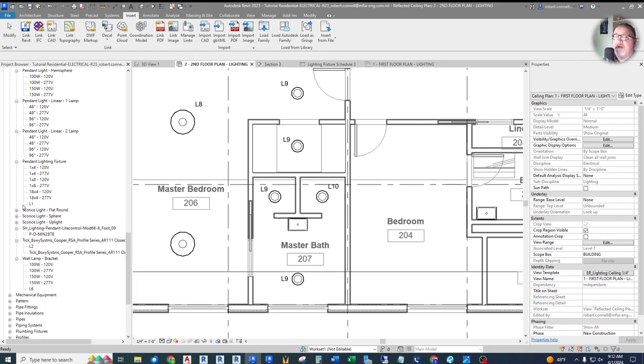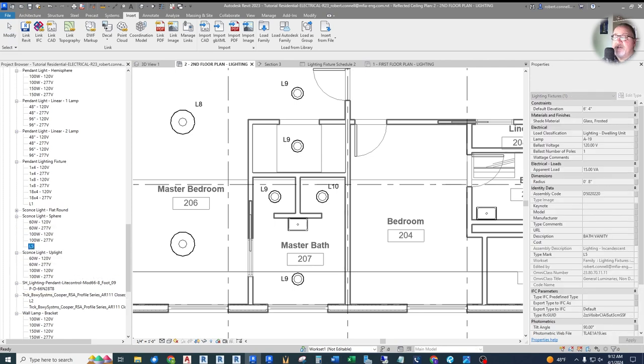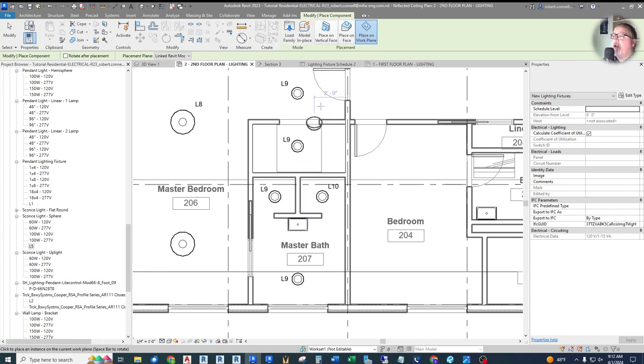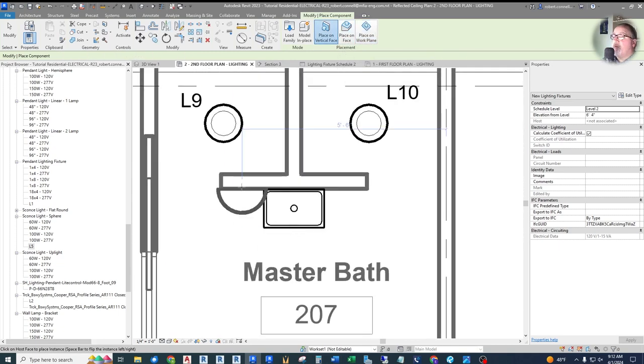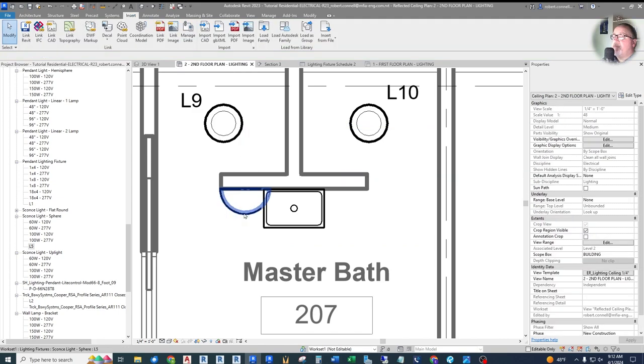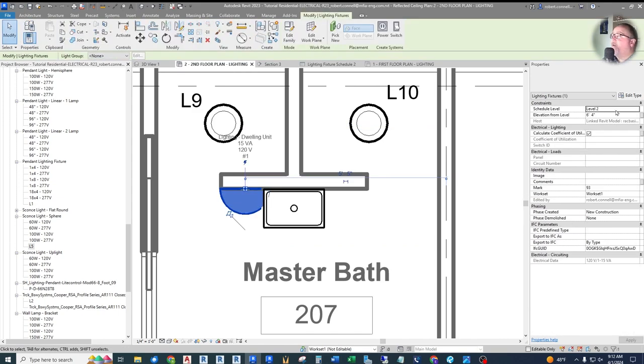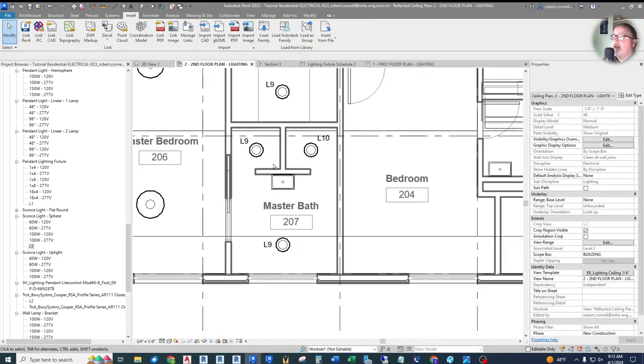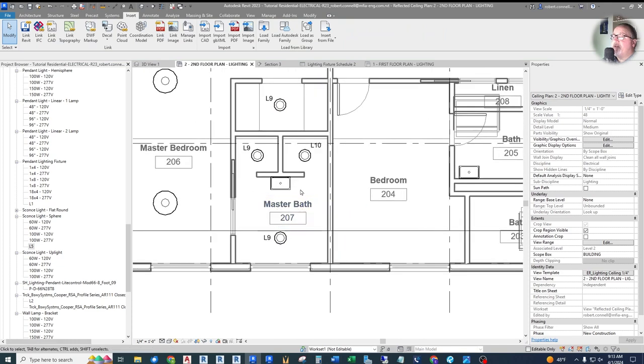Now we know Bath Vanity is L9. In the Project Browser under Lighting Fixtures, find L9 and drag it into the model. It's a hosted family, so choose Place on Vertical Face. Place it on the wall above the sink area at around 6 feet 4 inches, then drag it over the sink location. That light is now placed in the bathroom.